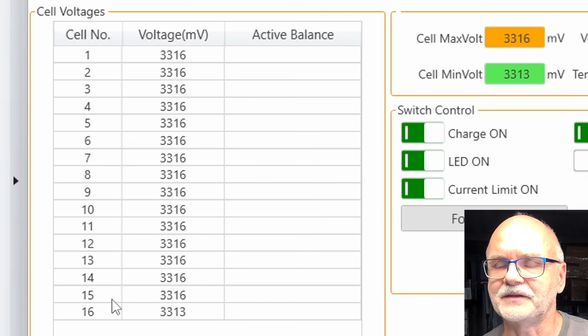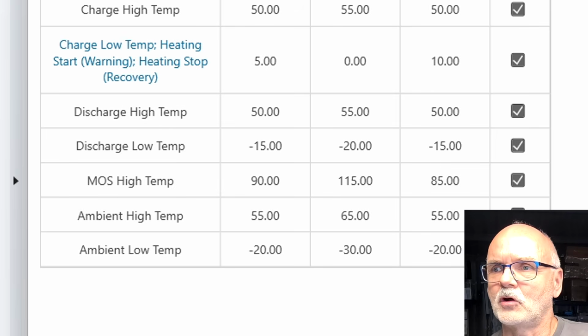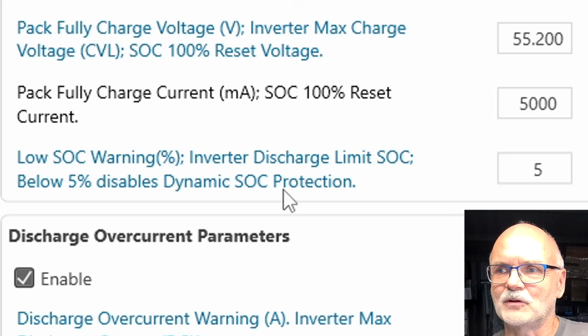There is another feature which I have hinted on, which is called the Dynamic State of Charge Protection. The thinking about this is actually pretty good. Usually in wintertime, what happens is you discharge your battery and it goes down to like 5 or 10%. You recharge it a little over the daytime, but there's not enough sun to fully charge it, so you probably get to 20-25%, and then sun goes down, you use this 20% again until the next morning. So you're cycling your battery in the very bottom all the time and never fully charge it because you're using this charge energy all the time.